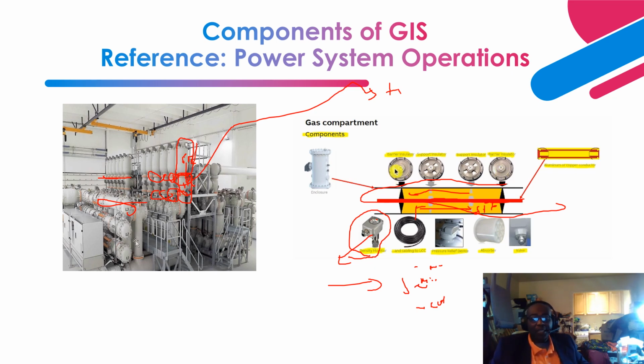Next, it's a pressure relief device, right? Inside this enclosure, you can have an overpressure condition due to a fault. So this pressure relief device, PRD, is what helps to relieve that pressure in the enclosure, just like the pressure relief device that you see in a power transformer.